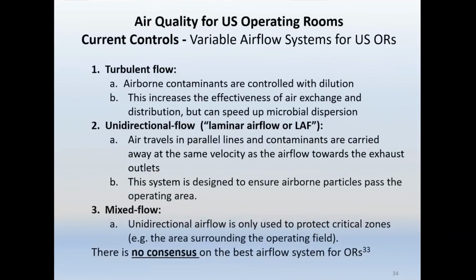The second is unidirectional flow, sometimes called LAF or laminar airflow, where air travels in parallel lines and contaminants are carried away at the same velocity as the airflow toward the exhaust outlets. As I showed earlier, this won't work at all if equipment is blocking those exhaust outlets, preventing air from leaving the room and being recirculated to achieve the needed 20 air exchanges per hour. This system is designed to ensure airborne particles pass out of the operating room to be filtered.